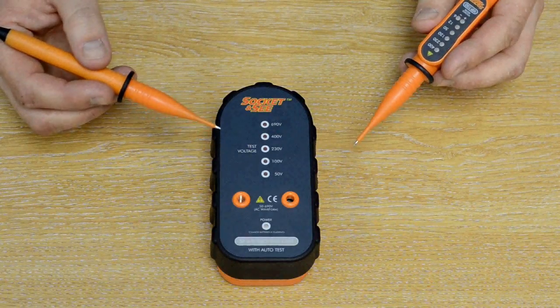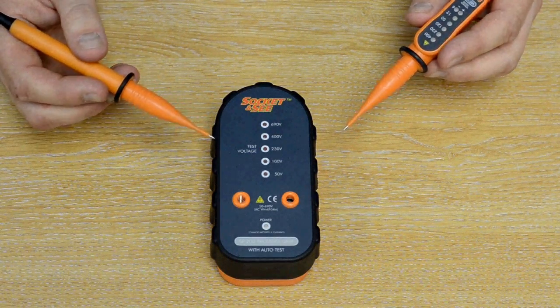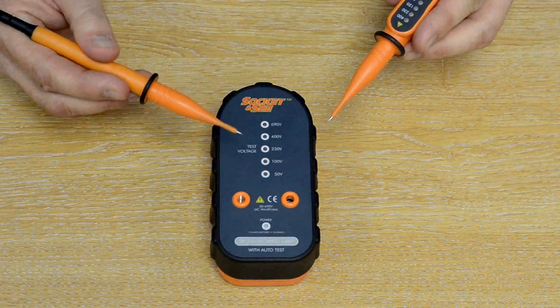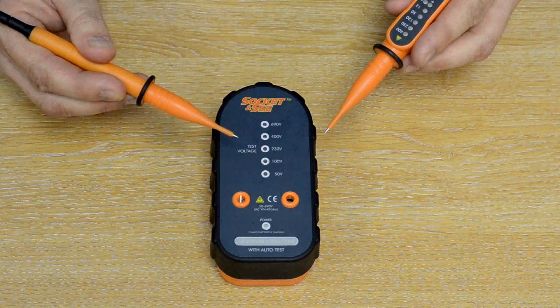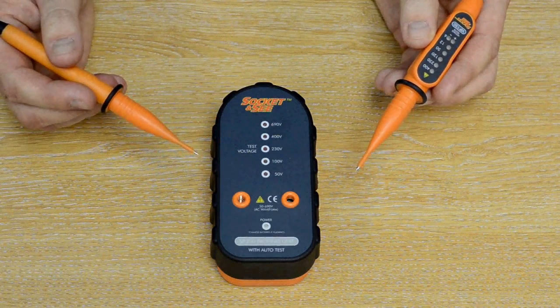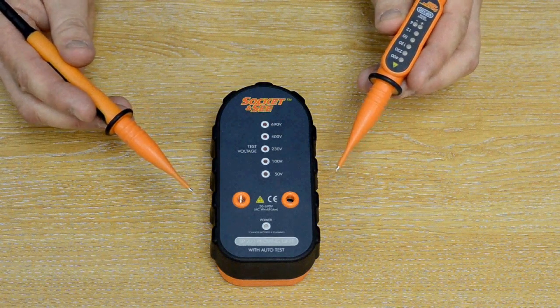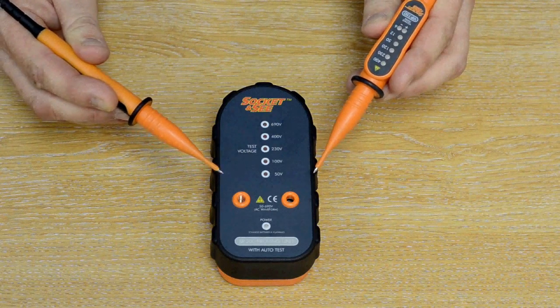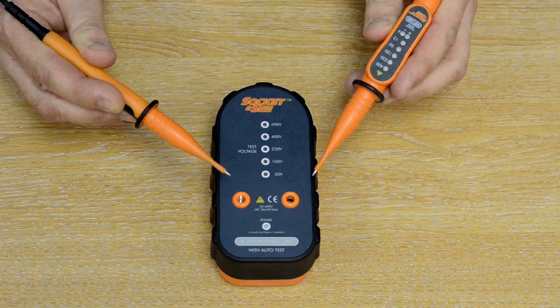As we talked about earlier, safe isolation practice dictates that you should test your tester on a known live source before attempting to test on a circuit. Here we're going to demonstrate using the Socket & See SP200 in use with the VIP 150 before we go to the circuit, and we will also test it after we come back from testing the circuit.